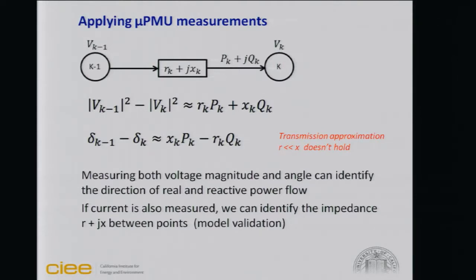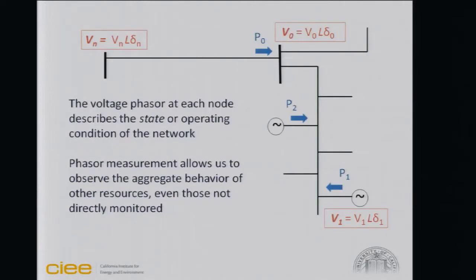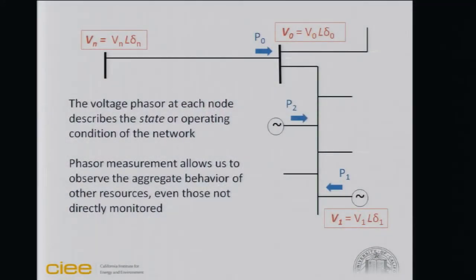The good news is that by measuring the voltage angle in addition to the magnitude, you can deduce real and reactive power flows in a way that measuring magnitude alone doesn't let you do. If we look at this in a schematic framework, measuring the phasor at a particular node can tell you about power flows from points on other branches of the network you're not directly touching. For instance, looking at the difference in the voltage phasor between V0 and V1, I can see something about what P2 is doing, what the other generator is doing, because it affects that phasor profile along the circuit.